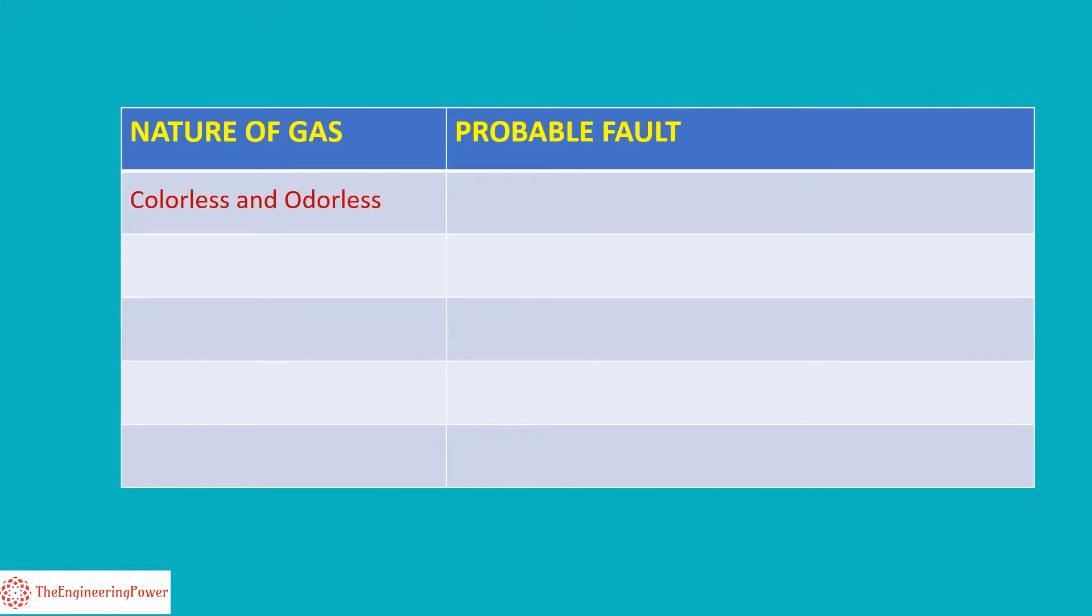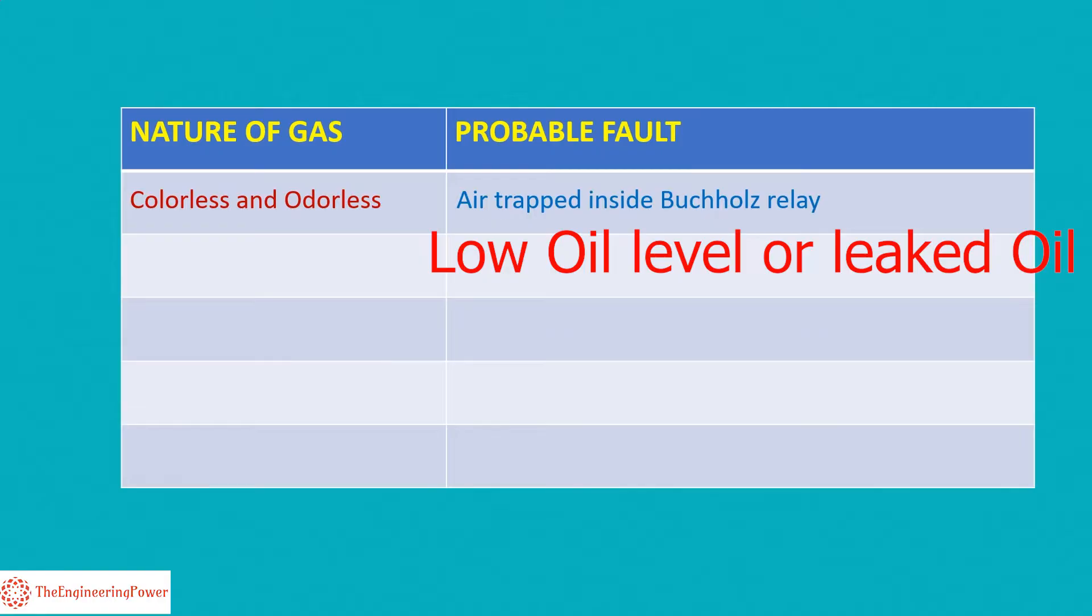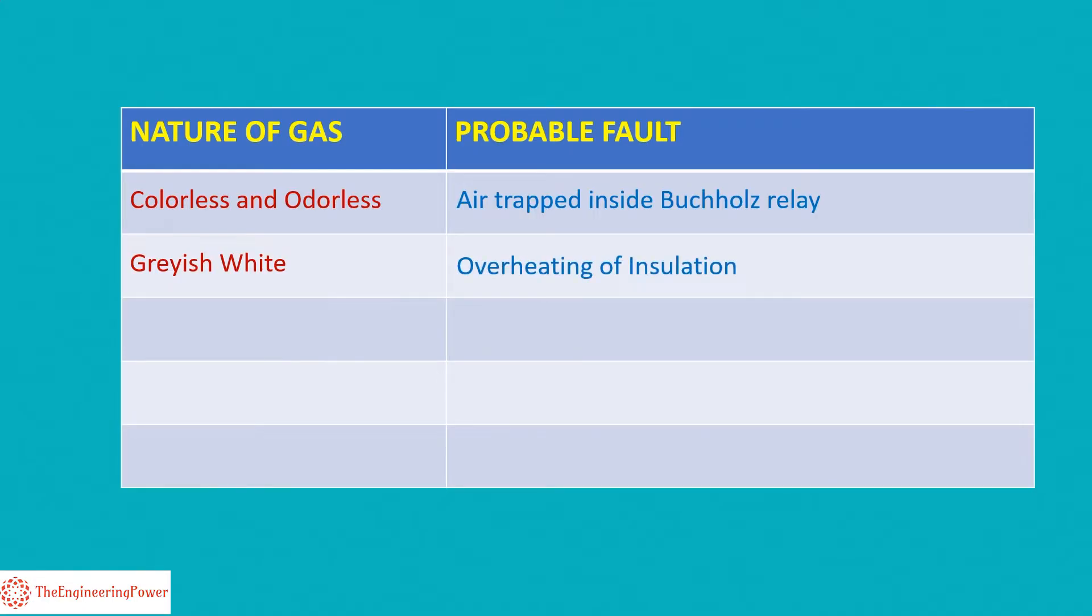When the gas is colorless and odorless, it means that there is air trapped inside the Buchholz relay that may be due to low oil level or leaked oil. Grayish white color of the gas means that the insulation is overheated. Yellowish color of gas means decomposing of wood or cardboard insulation.